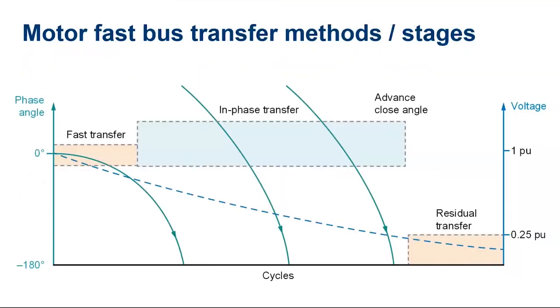The first one, the fast transfer, is when the motor bus is switched onto an alternate source with no intentional delay. It is initiated at a very high speed before the motor on the bus has a chance to slow down. That's the first mode, fast transfer. The next one is the in-phase transfer. In in-phase transfer, the relay looks for the alternate source to be in sync with the residual voltage on the motor bus. The transfer will be initiated when both voltages are in phase, and thereby it minimizes the transient torque on the motors. The third one is residual transfer.